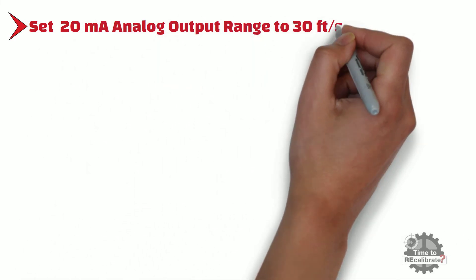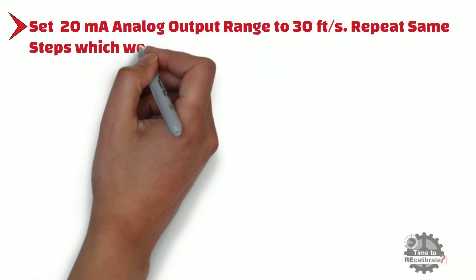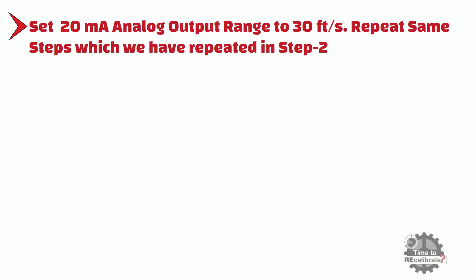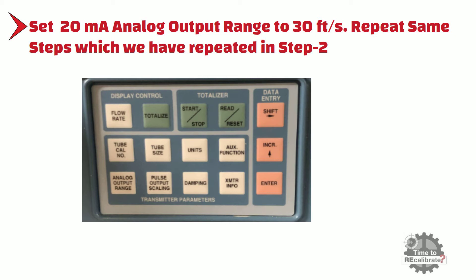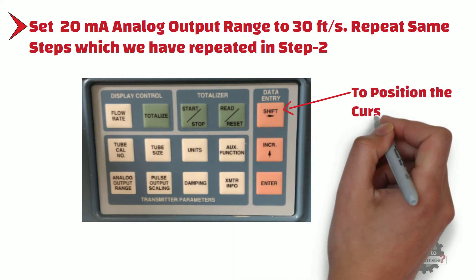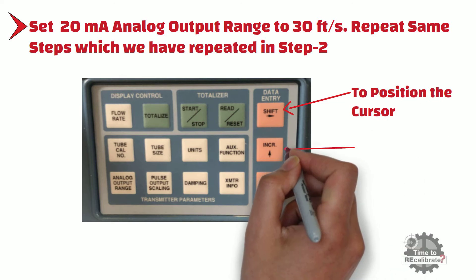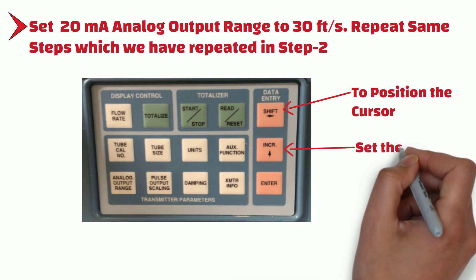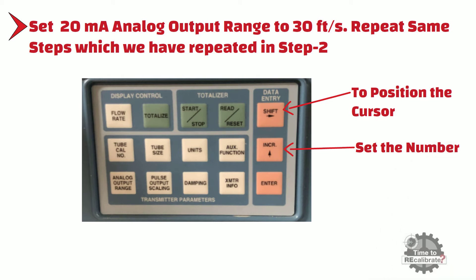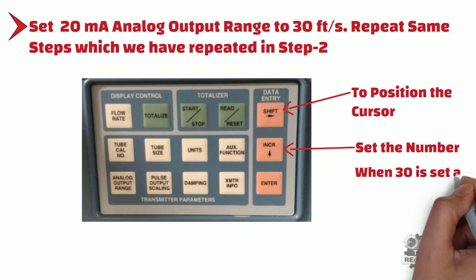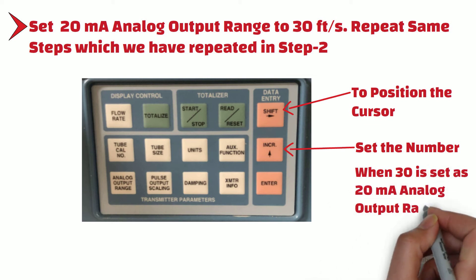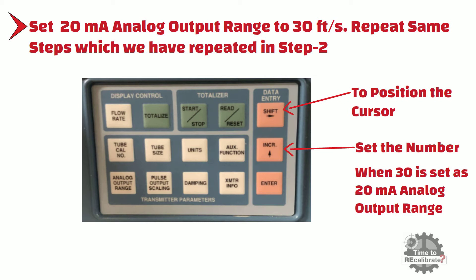Step 3: Set the 20mA analog output range to 30 feet per second. Repeat the same steps as in Step 2. Press the analog output range button — the current analog output range will display. Press the shift button to position the cursor to the digit that needs to be set, then press the increment button to set the number. Repeat until 30 is set, then press enter to store this value in the transmitter.